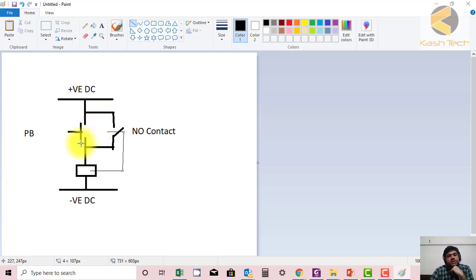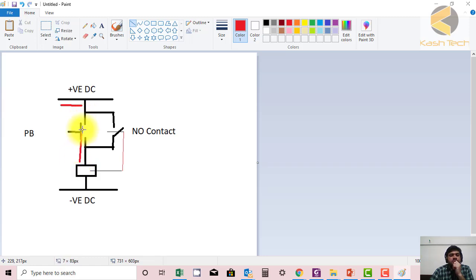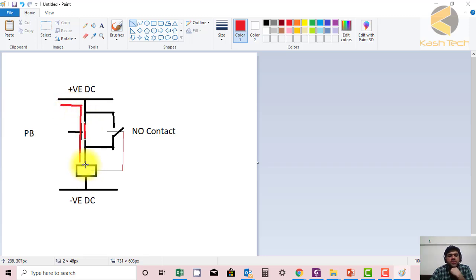So what will happen: this is solid positive, this is solid negative. As soon as I make this push button, DC will move from here to the relay through this switch. So now DC is moving here — when this coil is energized when this push button is operated. What I have done is I have closed this path, so DC is coming up and energizing the contactor. Now when the contactor is energized, because this is a normally-open contact, after it is energized this contact will be closed.